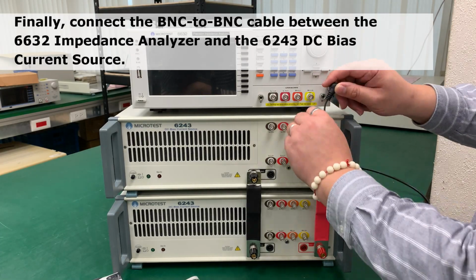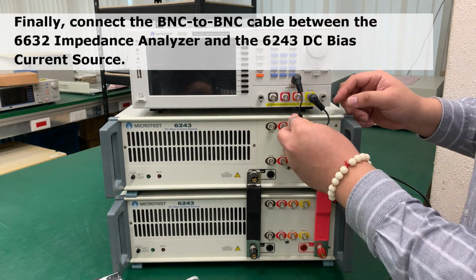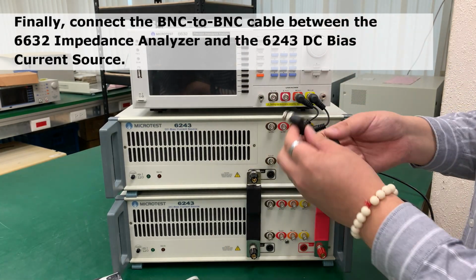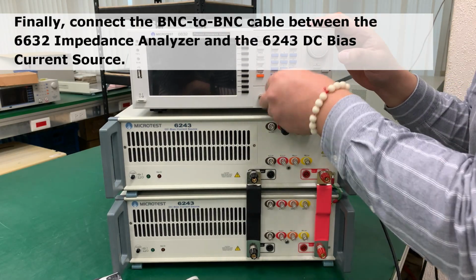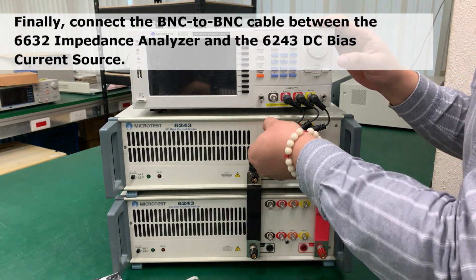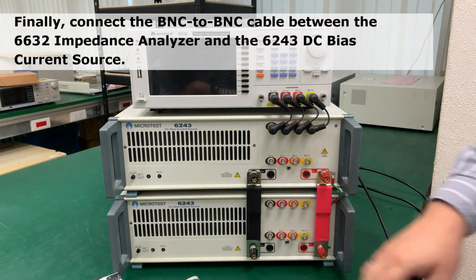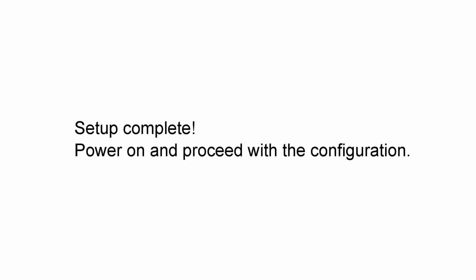Finally, connect the BNC to BNC cable between the 6632 impedance analyzer and the 6243 DC bias current source. Setup complete. Power on and proceed with the configuration.